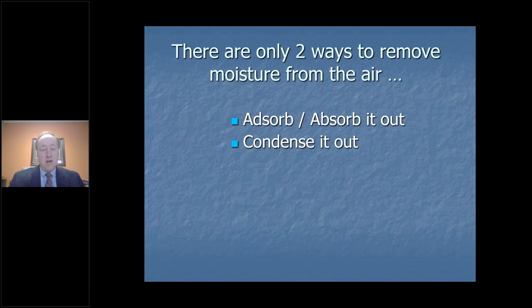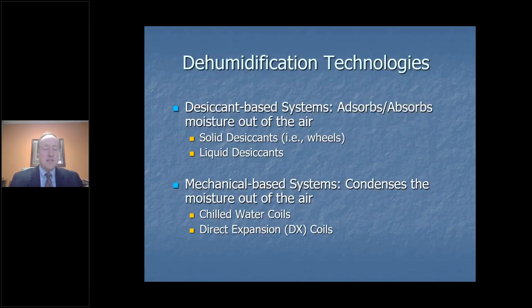And most people are very familiar with condensing it out, but not as familiar with adsorbing or absorbing it out. So here are the two technologies, the desiccant-based system, which again is solid, and we usually see that, at least in the HVAC world, in the form of a wheel. Or liquid desiccants, and you'll see this going through generators and regenerators. But we're just going to talk about this today because that's what we see mostly in the commercial markets. Then you see the mechanical systems. It may be chilled water based, it may be direct expansion based or refrigerant.